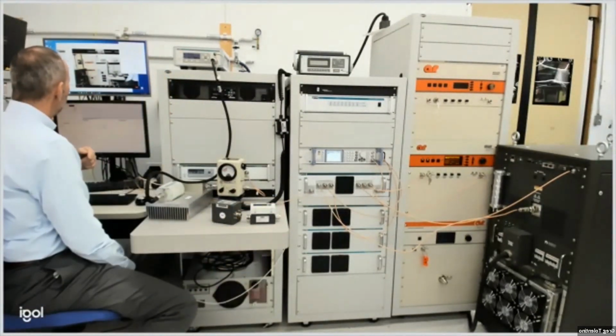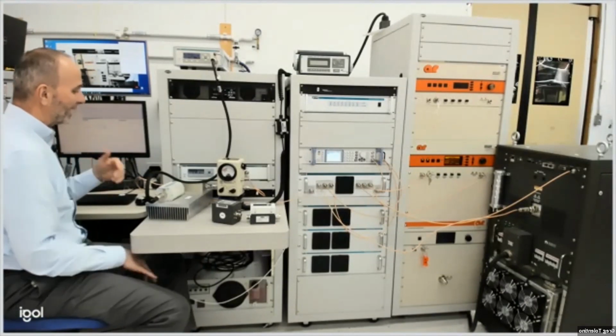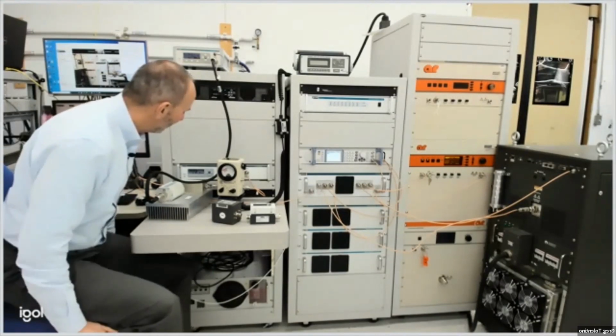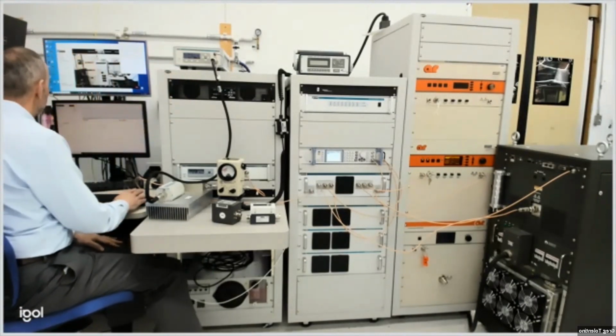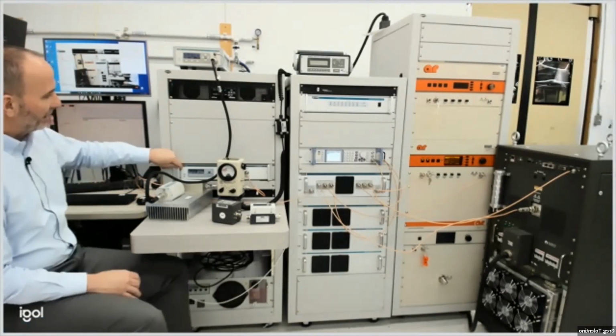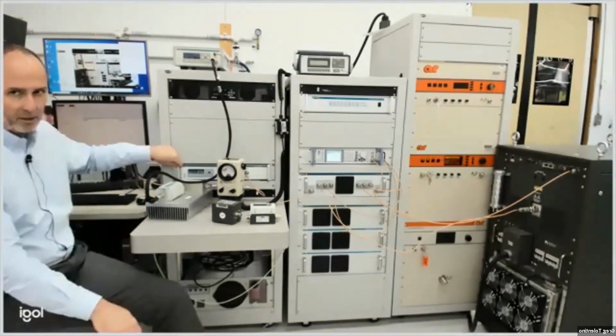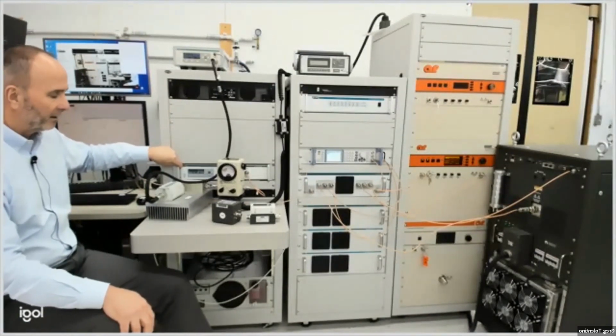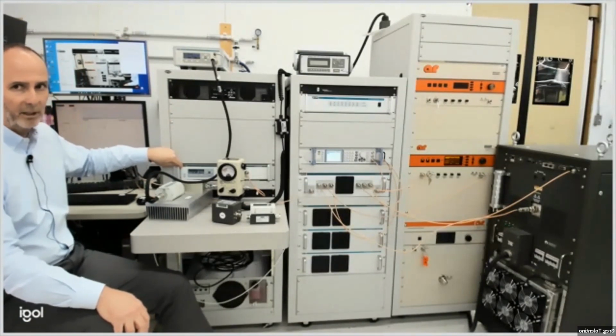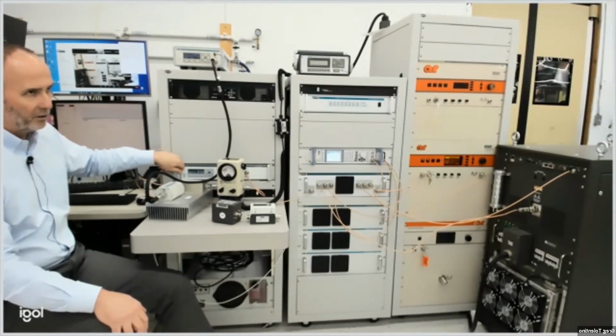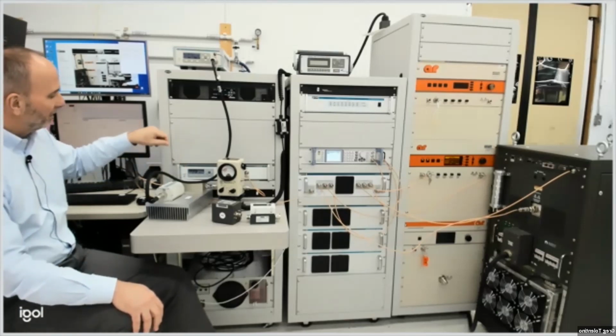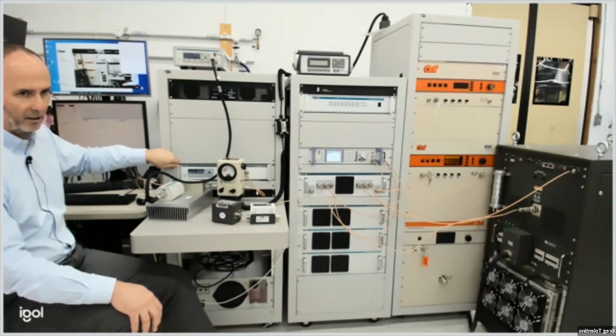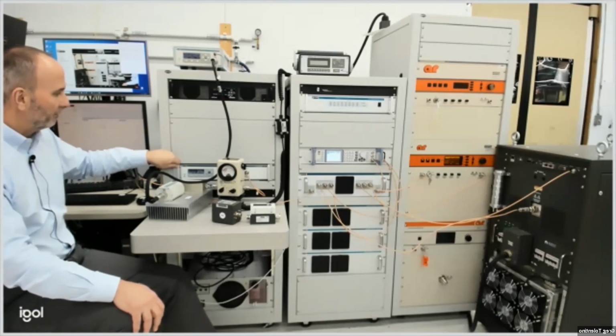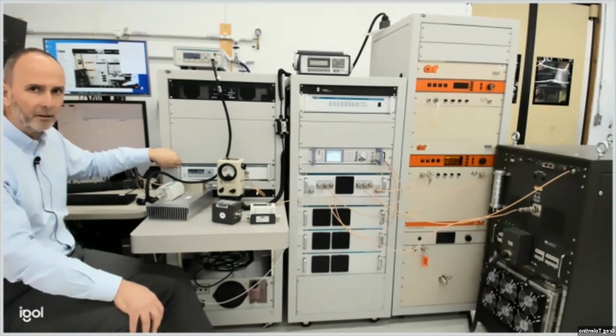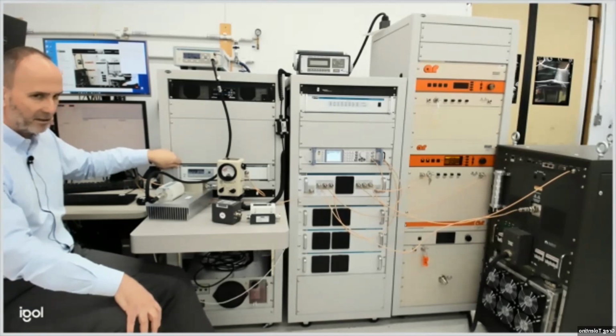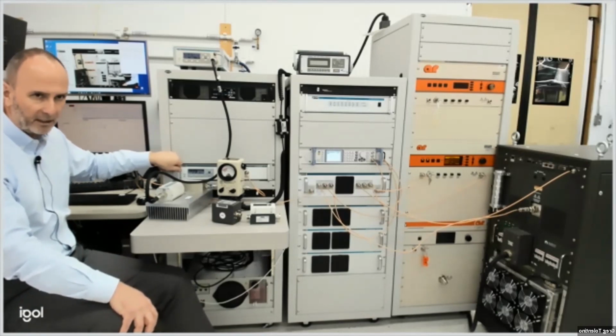We have a question. Does the software also have a routine built in to calibrate the calorimeter itself? And the answer is yes. Well, it's actually different software. The calorimeter is calibrated by precisely measured 60 hertz power. So you take a very well-leveled, regulated sine wave source, pass it through a revenue grade mains power meter into the calorimeter, and you essentially are calibrating the power linearity of the calorimeter. And we have a piece of software called HPC Cal that fully automates that into a hands-off process that then goes ahead and produces the cal table for the calorimeter.